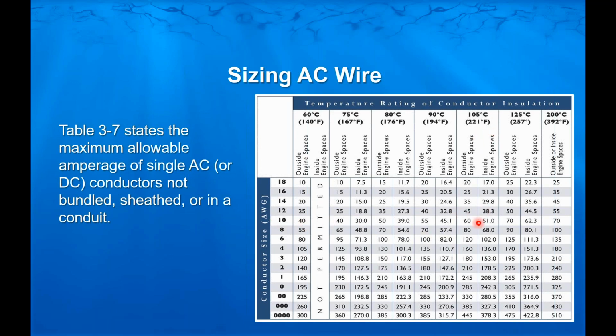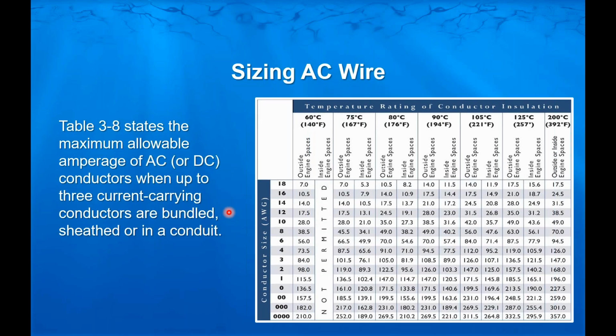So our 10 gauge wire, we come over to 105C. Outside an engine space says we can put 60 amps through that piece of 10 gauge wire. Inside an engine space, we can put 51 amps through that piece of wire. If we go to table 3.8, which is for up to 3 current carrying conductors, use our same 10 gauge, go over to the 105C cable. Now you can see, because we've added 2 other current carrying conductors, we're now only allowed to put 42 amps instead of 60 through the wire in outside engine spaces, and only 35 amps inside engine spaces. So as you can imagine, those subsequent tables that I mentioned, the more you add together, the lower this number is going to go for the amount of amperage that you can run through that wire, with it being included with many other cables.